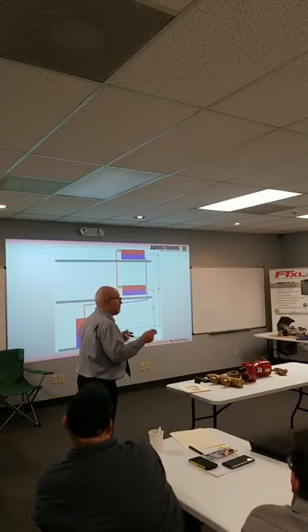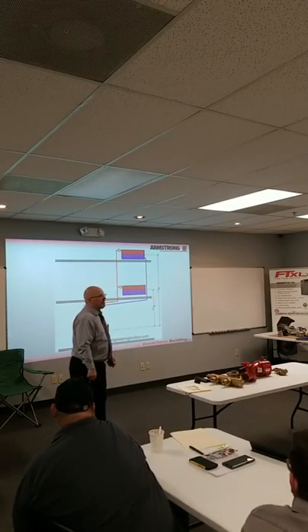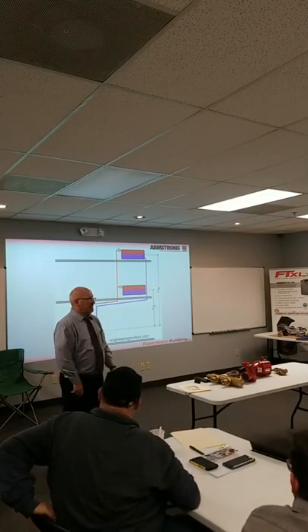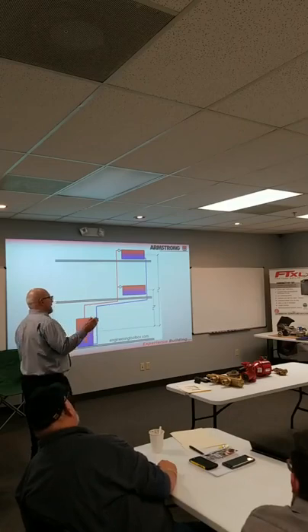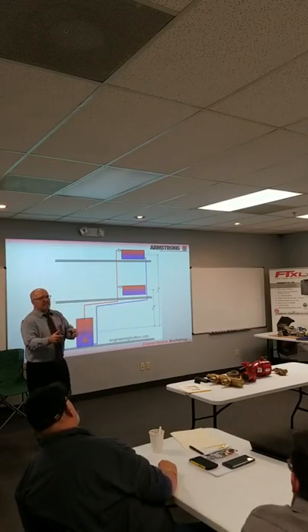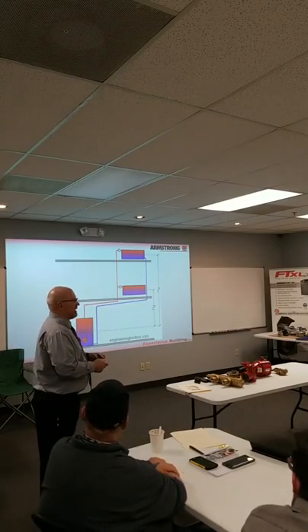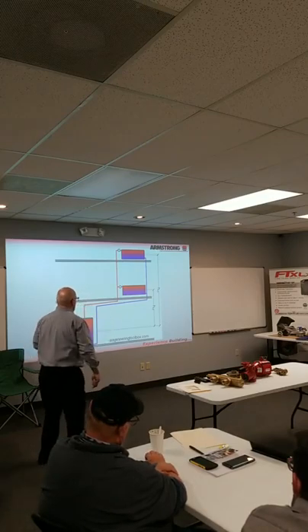It takes a little bit longer to heat up, but it's just nice, quiet, comfortable heat. Very nice. But all the heat doesn't go to the coldest room anymore. Right. So it's all about pipe size. The reason pumps were invented basically is because we wanted to buy smaller pipes because they were cheaper to run our distribution lines. So we needed to overcome that resistance. Just by gravity, it didn't happen anymore.